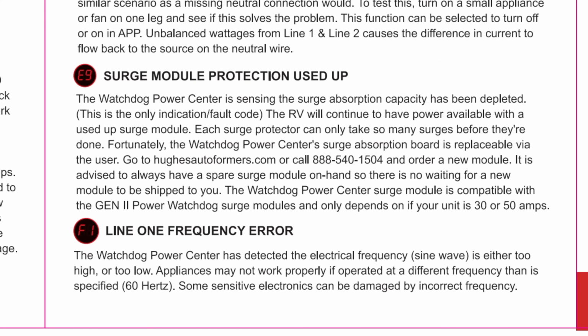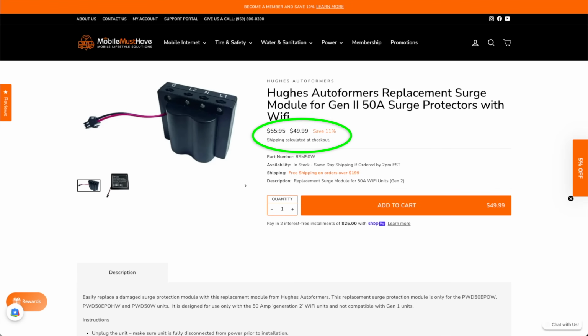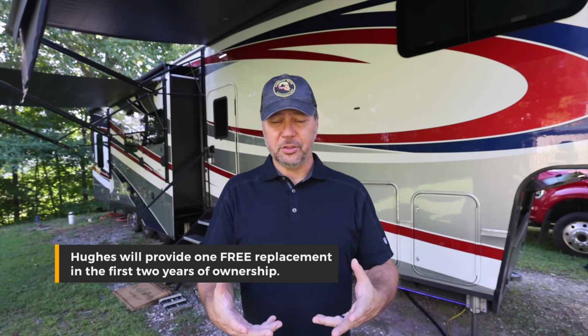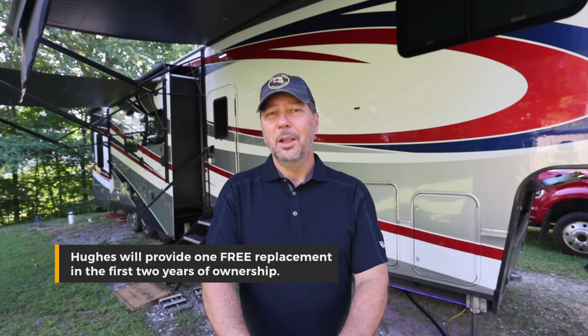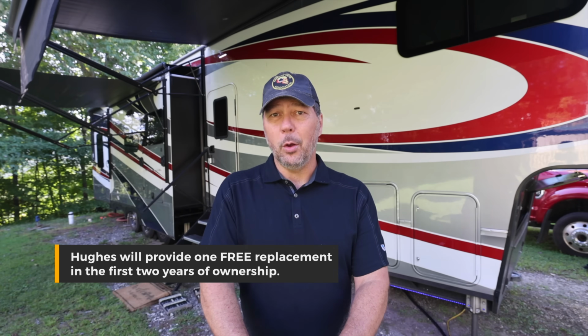Those could be 1,000 small surges over the course of a year, or one big surge from a lightning strike. When that happens, you'll get an E9 error code on this, telling you it needs to be replaced. You can pick one up for about 50 bucks last I checked, and swap it out yourself, which is awesome because it restores the surge capacity for about $50 instead of buying a whole new unit.